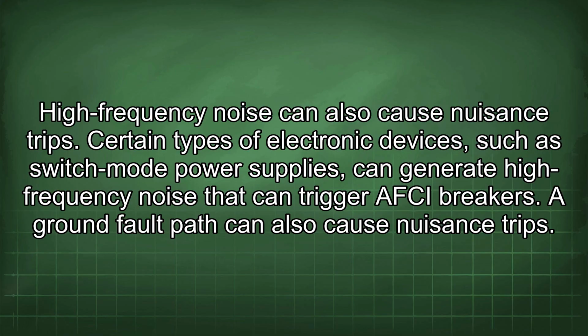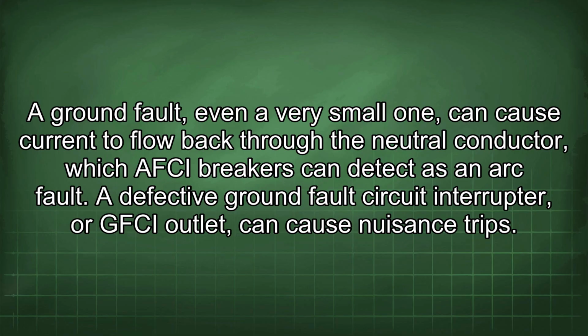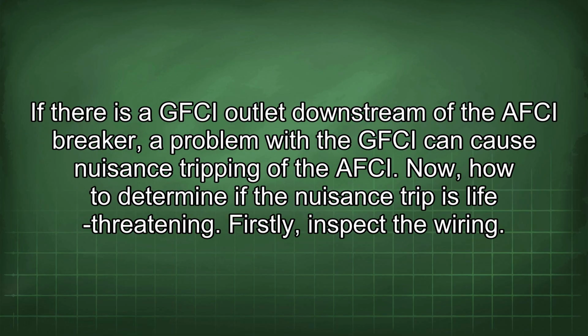A ground fault path can also cause nuisance trips. A ground fault, even a very small one, can cause current to flow back through the neutral conductor, which AFCI breakers can detect as an arc fault. A defective ground fault circuit interrupter, or GFCI outlet, can cause nuisance trips. If there is a GFCI outlet downstream of the AFCI breaker, a problem with the GFCI can cause nuisance tripping of the AFCI. Now, how to determine if the nuisance trip is life-threatening.